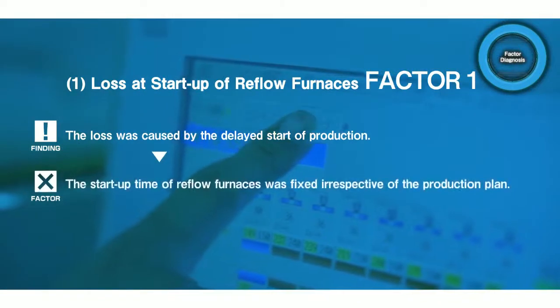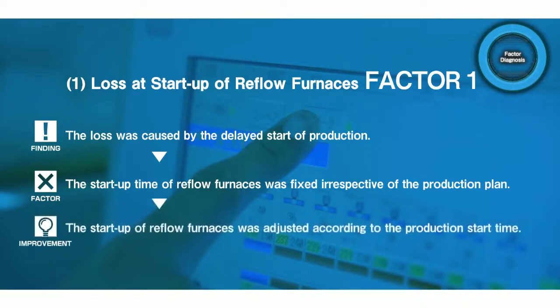When they checked the on-site operation, they found that the reflow furnaces had been started up at the same time every morning, irrespective of the production plan, as a matter of course from the past. As an improvement, they changed the operation to start up the reflow furnaces an hour before the production start time, according to the daily production plan.